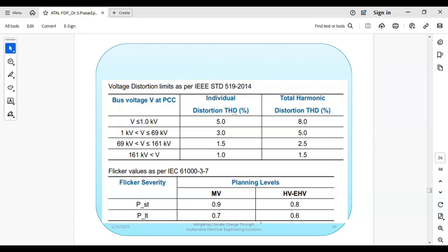So that report has to be used as input for the harmonic analysis. That means how much harmonics the source is generating, you have to put it as input, and then run the harmonics load flow. Basically, we are running harmonics load flow to investigate the total harmonic distortion at the point of interconnection. You need to conduct the harmonics load flow, which is available in DIgSILENT and ETAP software.